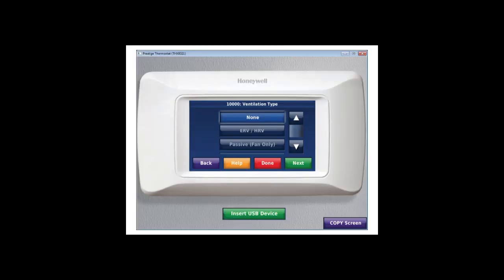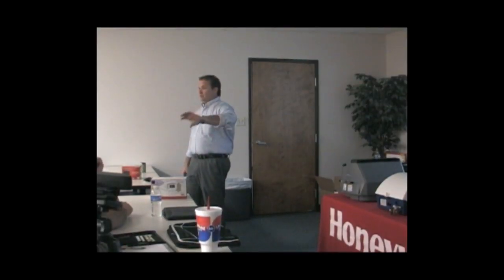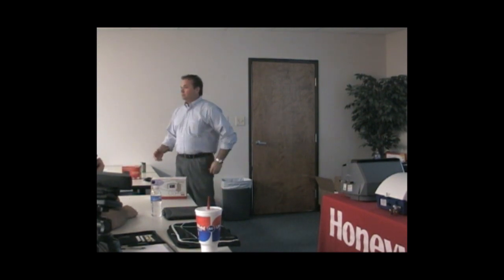So I can add an ERV or an HRV, or just put a piece of duct into my return and put a damper on it and control it that way. Is that like a fresh air module? Like a Y8150 that you buy so many of? Right, absolutely. And they do it because it's code.